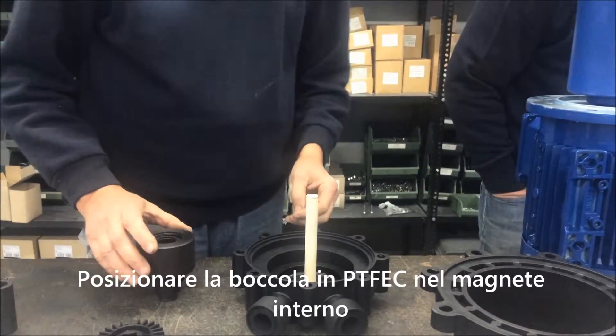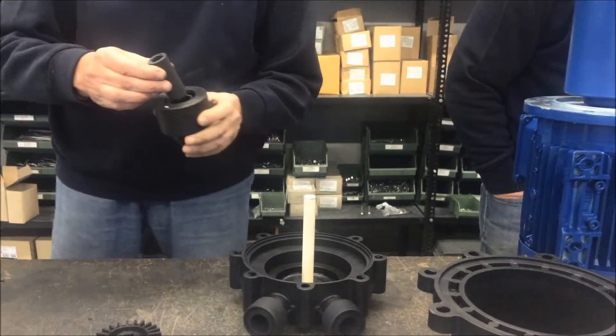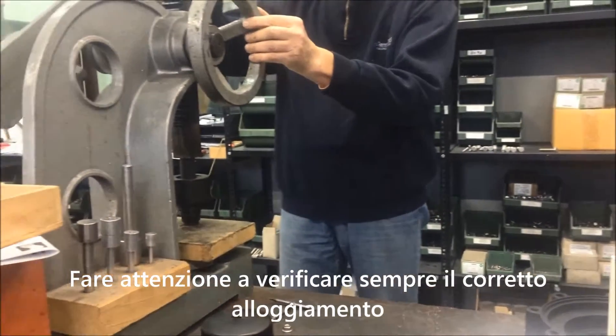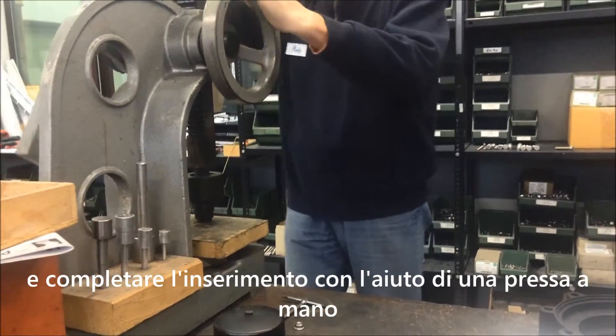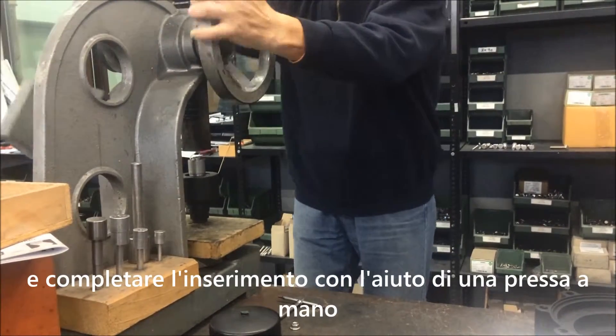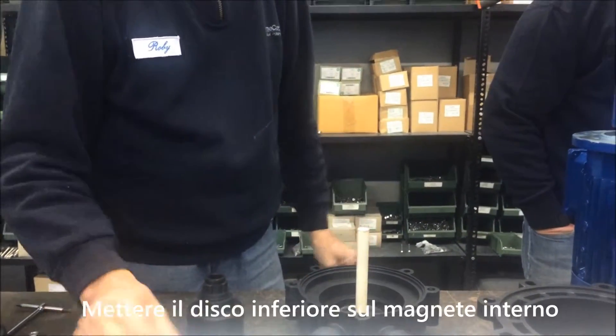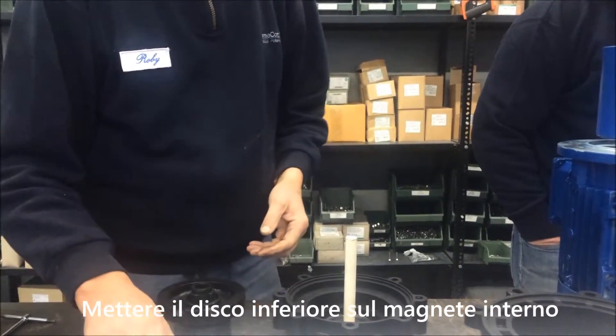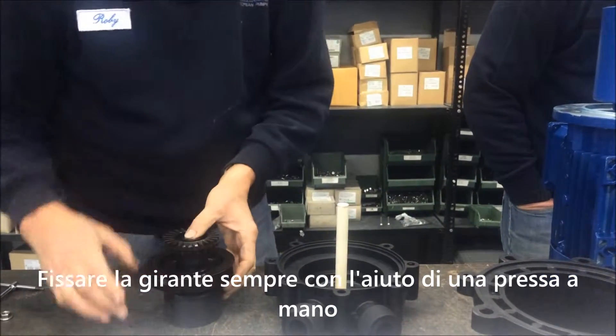Insert the PTFEC bearing into the internal magnet. Be careful to always verify the correct placement of the bearings, and then use a hand press for the complete introduction into position. Place the rear disc on top of the internal magnet. Fix the impeller and press them together with the help of a hand press.